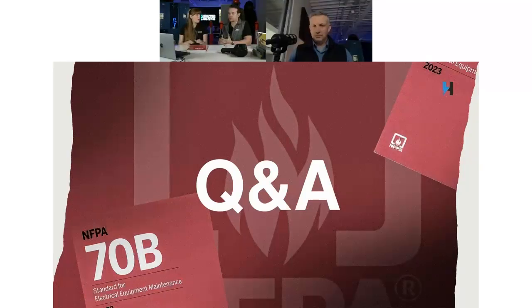So Jack, something that's really important that's taught in your certification class is to try and get the exact temperature as best you can. That's important, and it's sometimes time consuming, especially considering 70B is now expanded and you must follow most of it. However, 70B does not state you should use the exact temperature. It does state that similar electrical components under similar loading shall be compared for their temperature, and then compared between electrical components and ambient air temperatures.